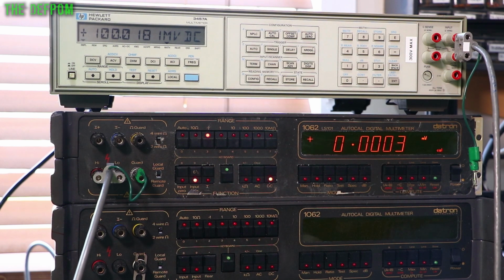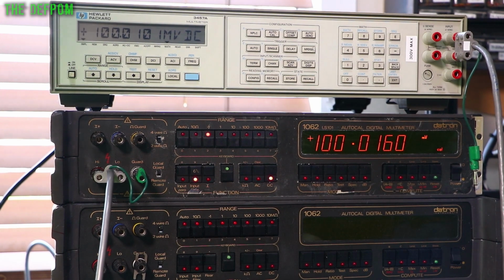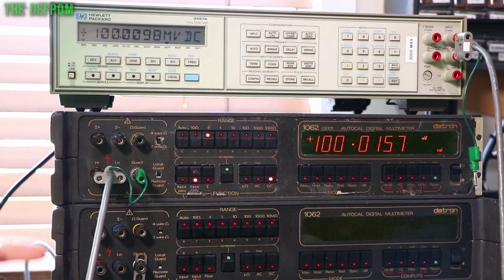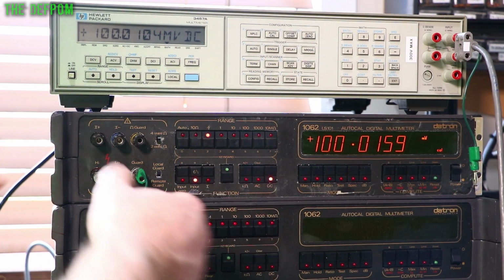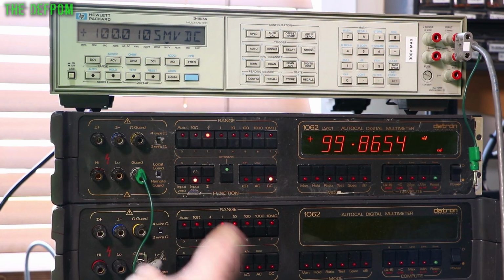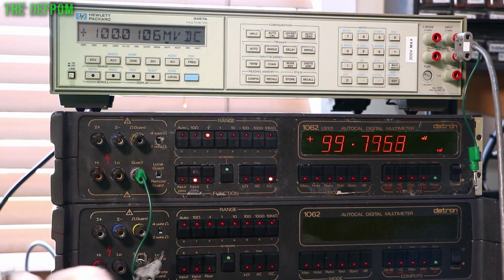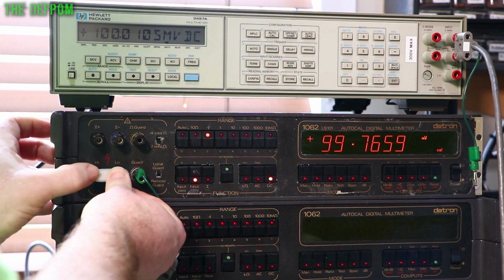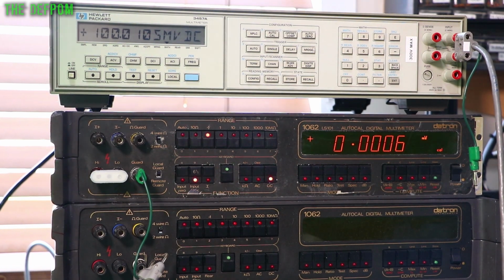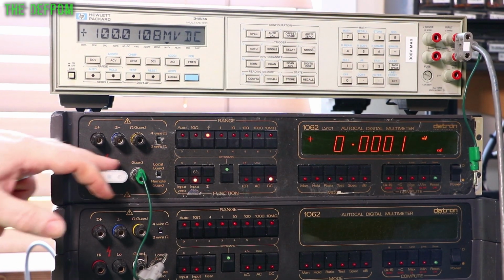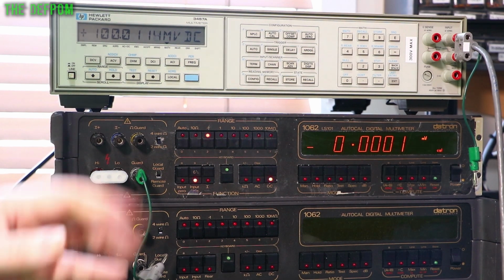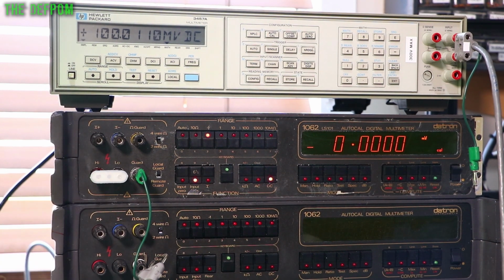That seems reasonable there, doesn't it? Yeah, I think I'll do. Next step. Now the next step's to do zeroing. So I've actually hooked it up to the DC calibrator again already. But what I'm going to do now, instead of using the zero on the calibrator, because the calibrator may be slightly off, is shunt the terminals together. Right, that means you've definitely got zero potential difference across the two inputs. And because I already did the zeroing yesterday, it should be pretty good.